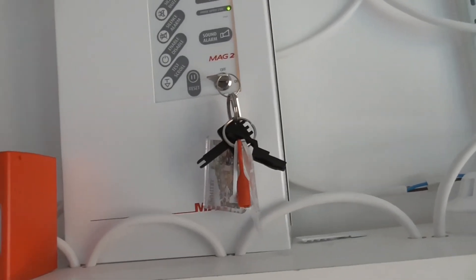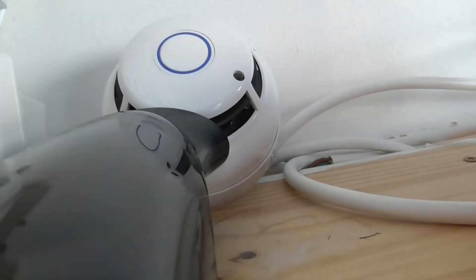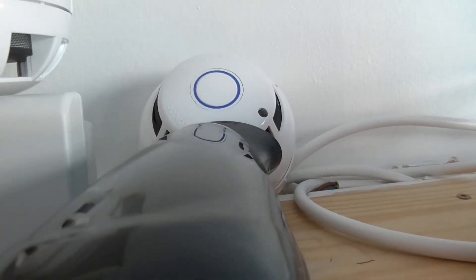Now we'll test the heat element of the multi-sensor Protec 3000 Plus. We'll give the multi-sensor test — let's see if it goes off again. Let's test the heat element. It doesn't feel too warm. Let's press reset and see if it goes off, which it shouldn't.